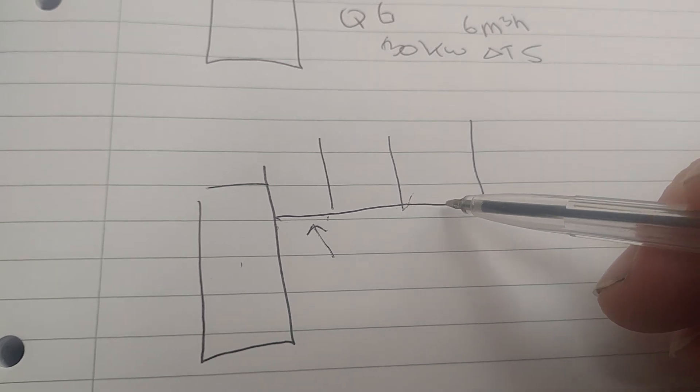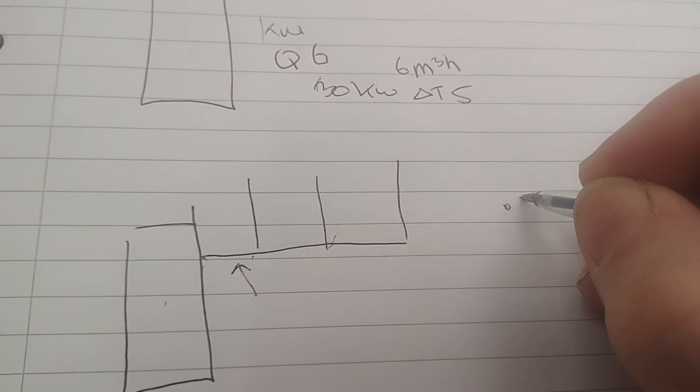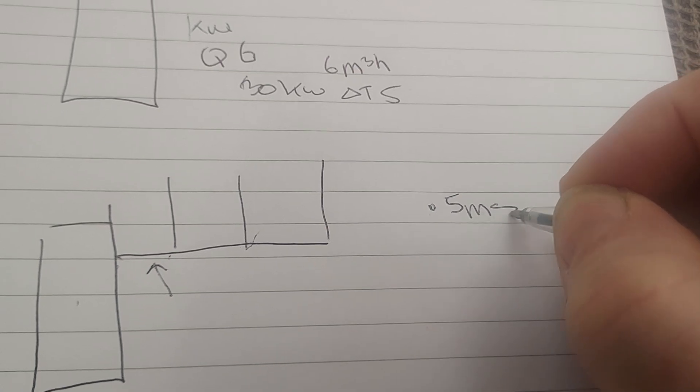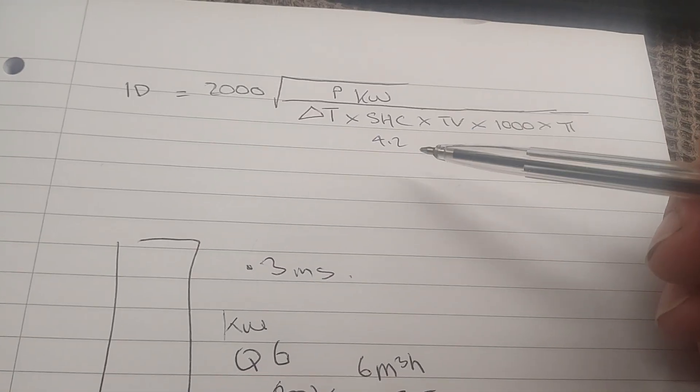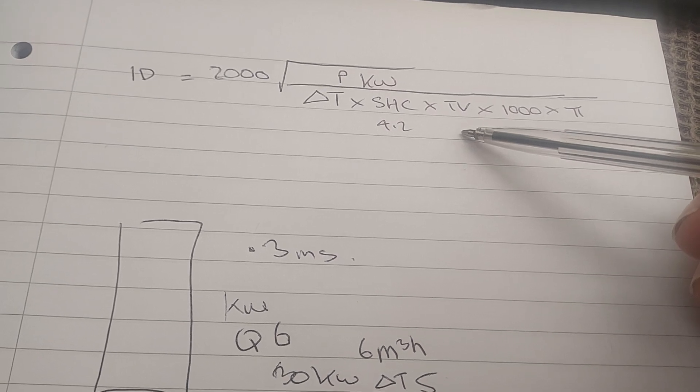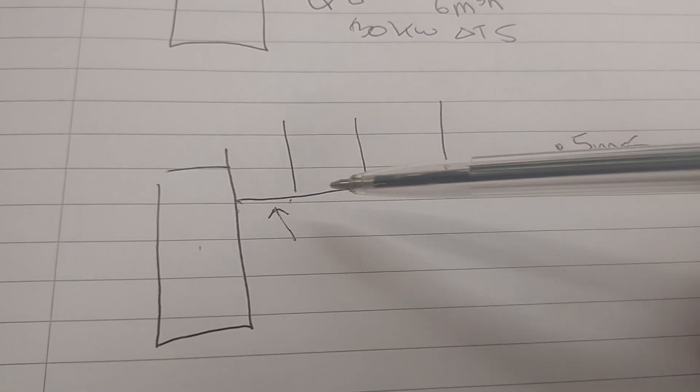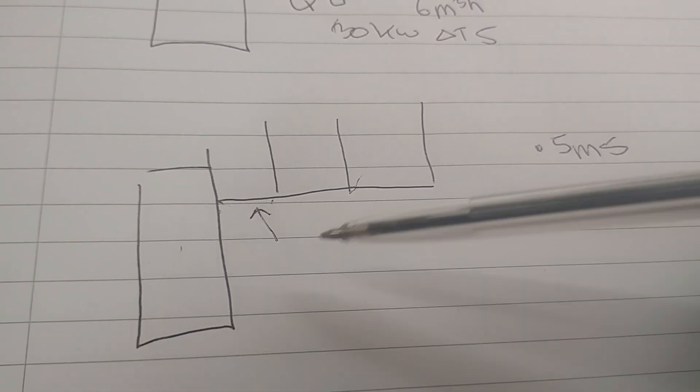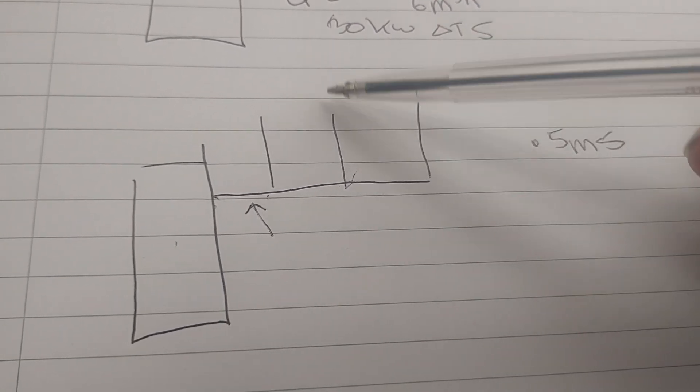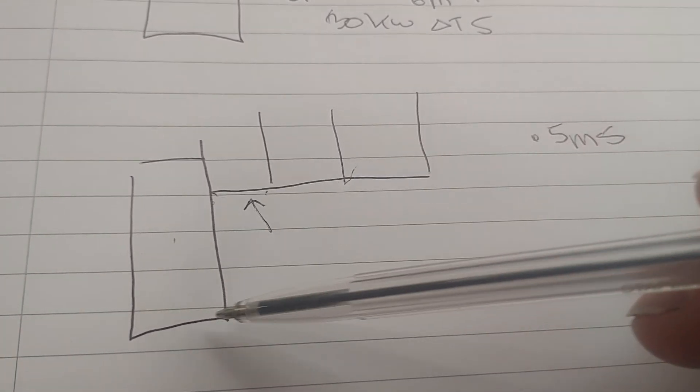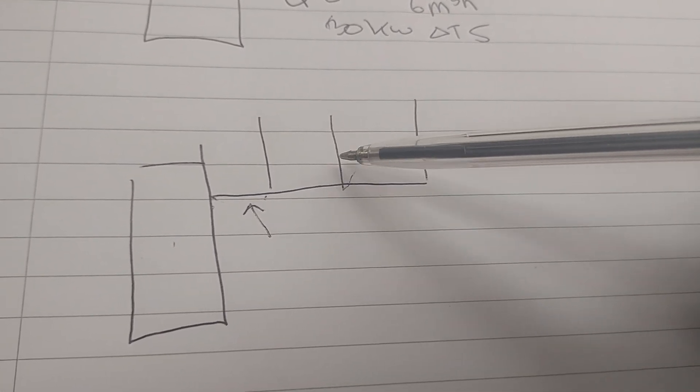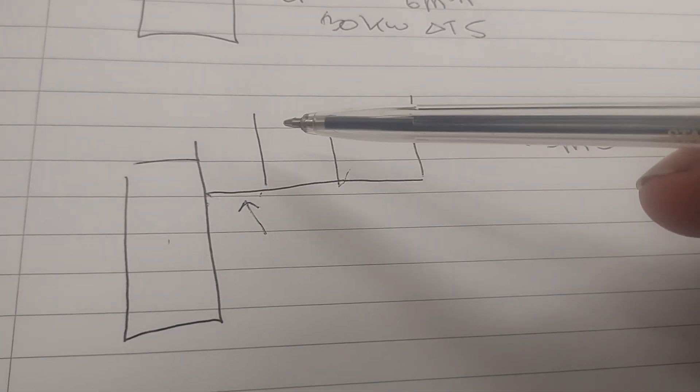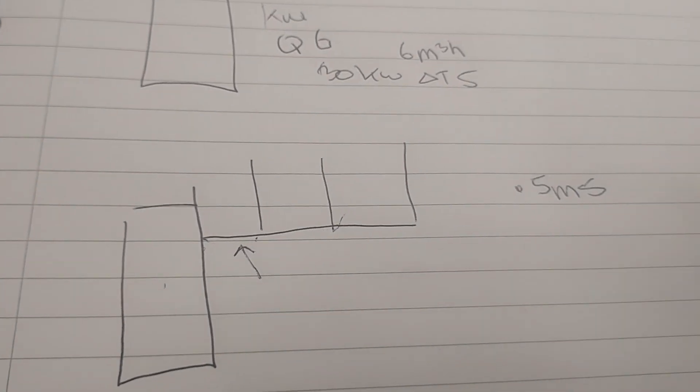It's going to carry the full load of all three circuits, and the velocity in the distribution header is 0.5 meters per second. So again in our formula we're going to put in the target velocity here of 0.5 meters per second. The point of these low velocities is to create low differential pressures. When you've got a pump running off on this circuit here, we don't want to see a pressure difference between these points or around through the other circuit. The idea is that the pump will apply a negative pressure on the inlet side of the pump and that's going to draw from the easiest spot.